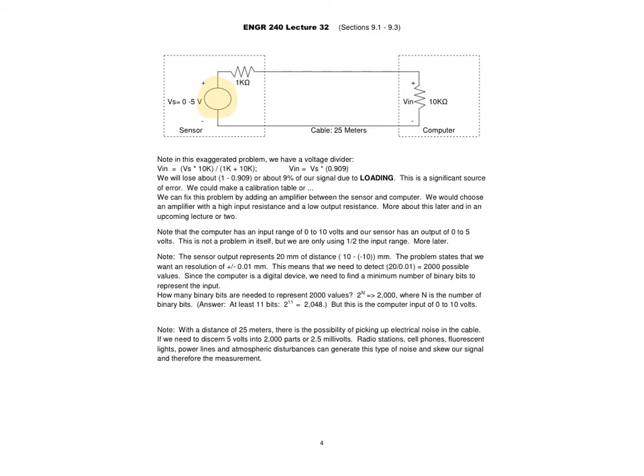What we have here is a voltage divider, meaning not all the voltage from our sensor makes it to the computer. There's a voltage drop across the 1K resistor, and using the voltage divider formula, the voltage seen by the computer, Vin, is a little over 90% of the actual signal. We can handle this a couple of ways: if we're doing a simple one-off rather than mass producing, we could build a calibration table, as long as we can accurately characterize the sensor and the load the computer presents.